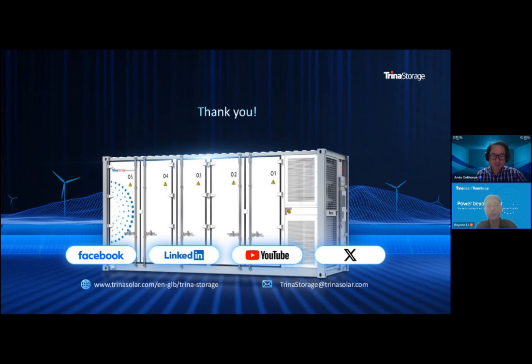So with all these tests, including the communication, functional, and safety design tests involving both the PCS and BMS, and also SMA's PPM (they call the EMS the PPM), we can implement a more well-founded protection scheme on the system layer. So our customer can be better assured about the exact performance before the Elementa 2 units are dispatched to the customer side. Yeah, thank you.